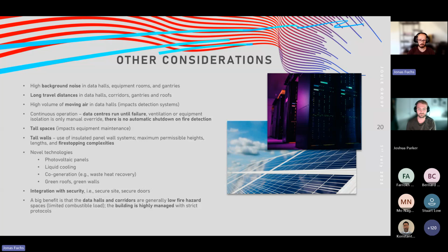Furthermore, there are also novel technologies being brought into these buildings, such as photovoltaic panels, typically on the roofs, liquid cooling, as opposed to air cooling. There's also cogeneration being brought to these sites, where obviously there's a lot of waste heat that's available and that can be used for other areas, such as municipal heating, such as pool heating, or anything you can think about. There are also green roofs and green walls often deployed on these sites. The one item that also needs careful consideration is integration with security. The entire site is usually highly secure, have a secure perimeter, secure doors, and it's difficult to get to the site, and it's difficult to leave the site, and also needs to be considered with regards to door unlocking, fire alarm, signaling, etc.